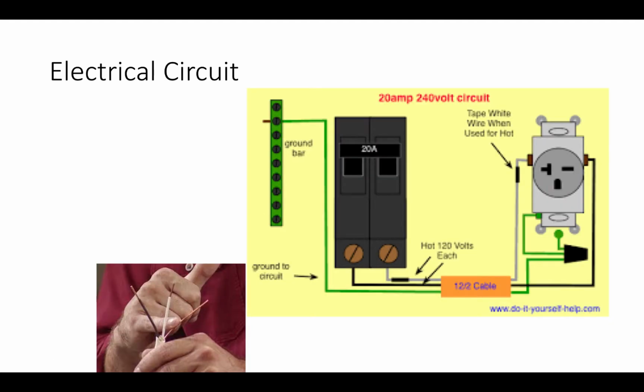Okay, so we have an electrical circuit. If you take a look at the picture on the bottom left, this is an example of a Romex conductor. We have a black wire most often, we have a white wire, and we have an uninsulated wire, that's our ground. Okay? So in a 20 amp, 240 volt circuit, we will have two hots and a ground. The ground is always connected to the frame, to the ground rods outside, and a ground bar. Okay, ground is uninsulated most often.